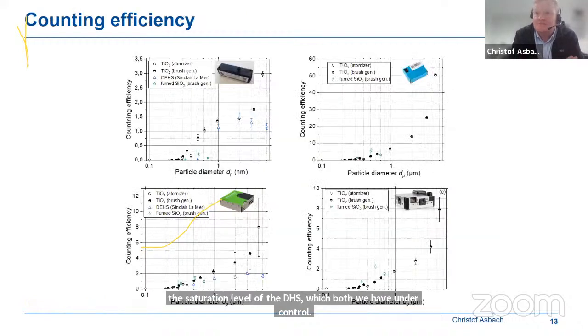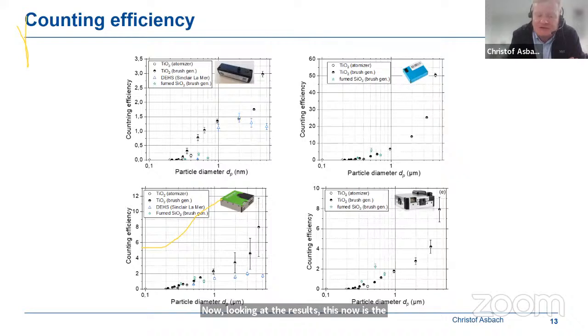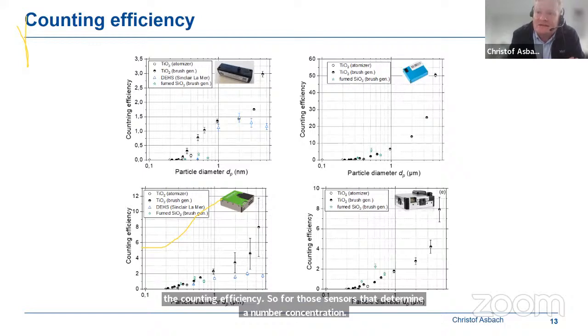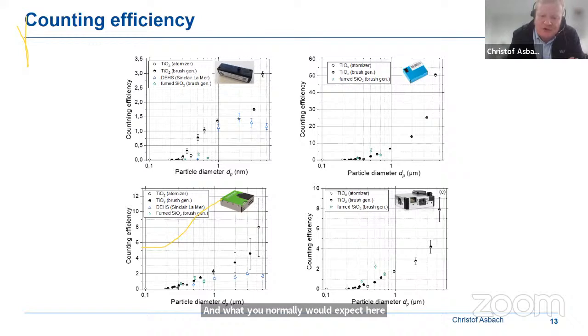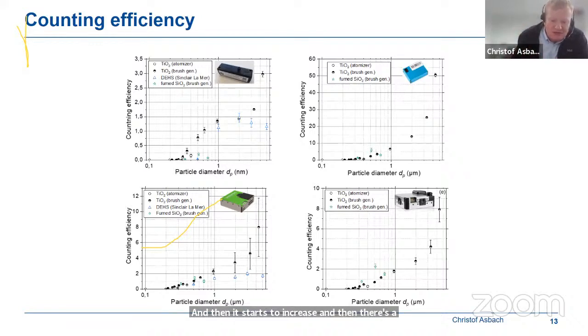Now, looking at the results, this now is the result for the counting efficiency for those sensors that determine a number concentration. And what you normally would expect here is the typical S-shaped curve. So the counting efficiency is 0, and then it starts to increase, and then there's a D50, which I assume to be 0.3 microns, because that's what the manufacturers deliver as the lower detection limit. So at 0.3 microns, we would expect to see 50% detection efficiency, and then it further increases to a detection efficiency of 1, and then reaches a plateau and remains at 1.